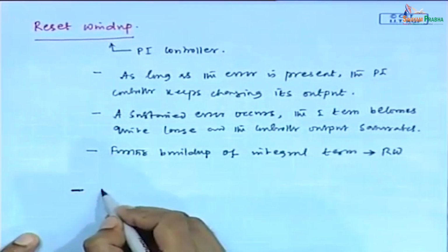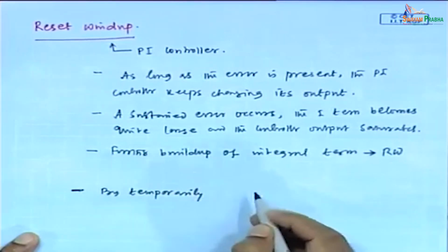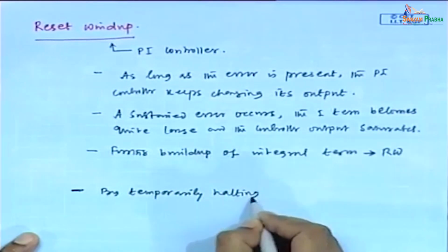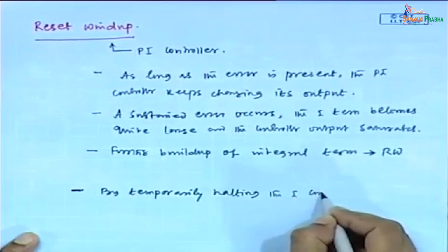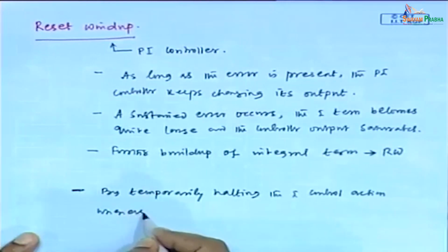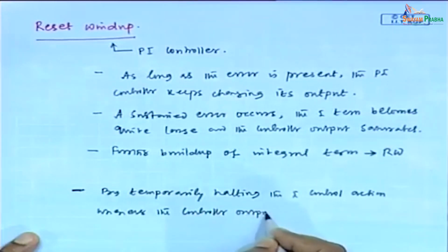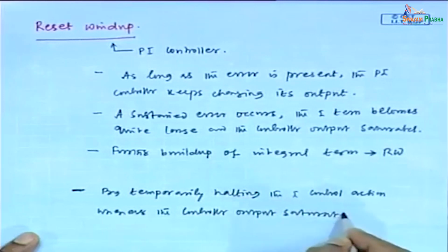Reset windup is reduced by temporarily halting the integral control action whenever the controller output saturates.